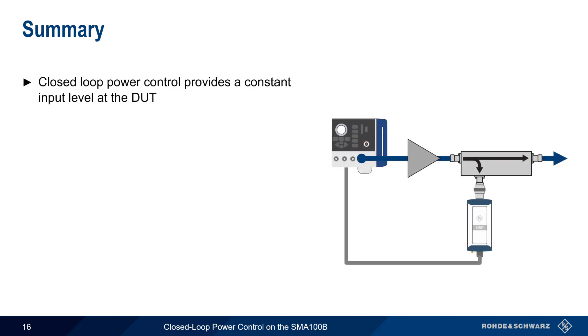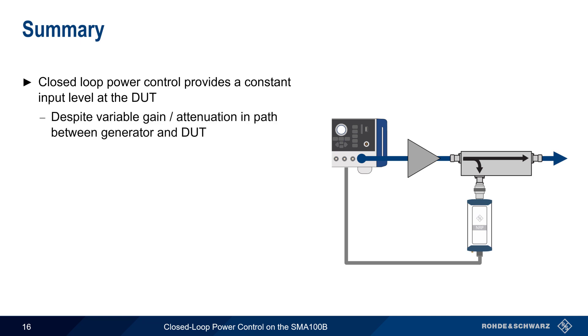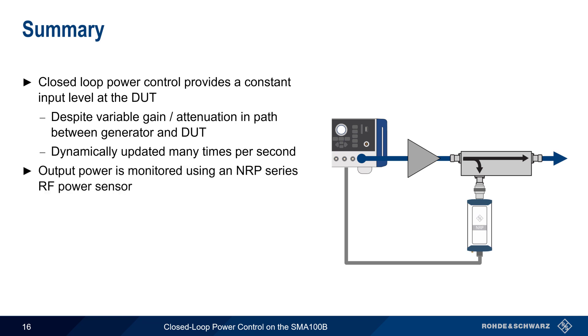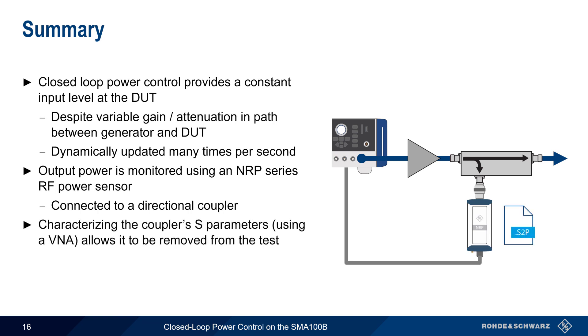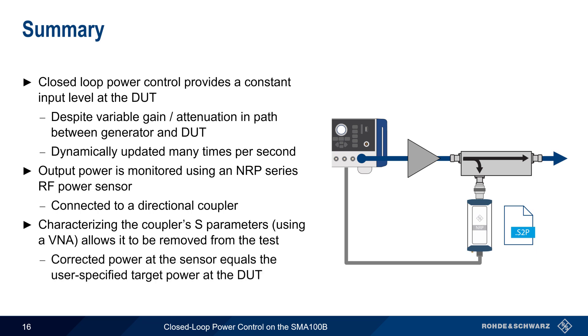Let's end with a brief summary. Closed-loop power control provides a means of maintaining a constant input power level at the device under test, even if the gain or attenuation in the path between the generator and the DUT changes. Power can be dynamically adjusted in real time, many times per second. An NRP series RF power sensor is used to monitor the power by means of a directional coupler. The coupler can be characterized using a VNA, and the resulting S-parameters can then be loaded into the power sensor, simplifying configuration by making the corrected power reading at the sensor the same as the user-specified target power at the DUT. Although this presentation has shown how to configure closed-loop power control on the SMA100B, please note that it is also supported on most other Rohde & Schwarz signal generators.